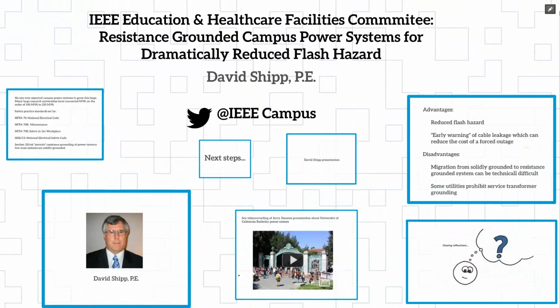What I'm using, where I'm starting to get some headway, at least in the other industries, is the incident energy one. If I do it the old way and have very high incident energies, like in the lighting panels, where more, less qualified people are acting in it, if I have a 15 kVA isolation transformer feeding that one lighting panel, the incident energy is down in the dirt. If I don't have the transformer, just do it at 480, 277, I've got to have a spacesuit on, or I have to turn power on that feeder off completely just to change the feeder circuit breaker out of the panel board in the hallways.